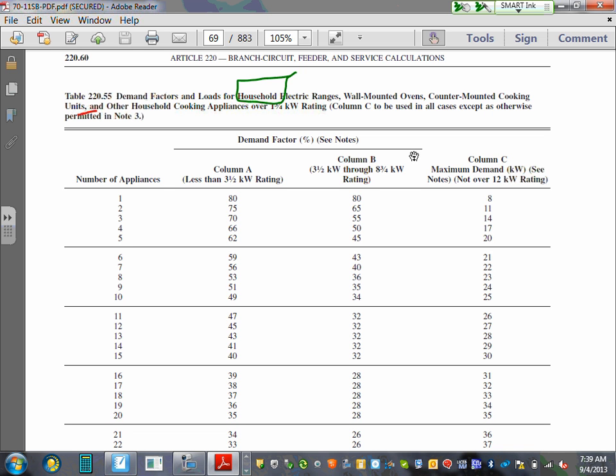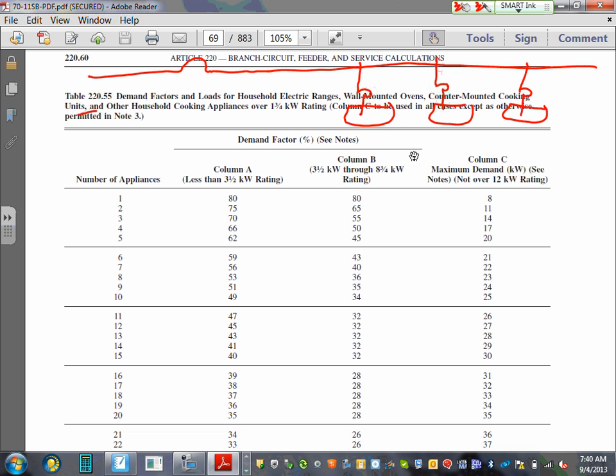Okay, let's take an example. I'm going to take a combined example, guys. Very easy. And let's take it right here. So here's my feeder coming in here and feeding a bunch of loads, right? From a panel, a bunch of loads. And all these loads are inside a panel. This is like, say, the panel that you guys are sizing with your friend Chad, right? And you need to size the feeder that feeds this panel.